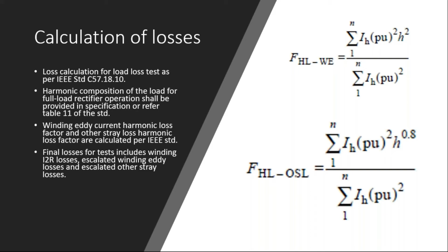And when it comes to testing, Parminder can talk about this, the additional losses we need to feed during the heat run test. Yeah, so based on the K-factor, harmonic losses are determined by engineering. For the temperature rise test, those are actually fed in addition to the load and no-load losses. The total losses which are fed during the temperature rise test are more than the total losses of the transformer which we generally calculate. So it is a combination of no-load losses plus the harmonics. That's how the temperature is simulated in the transformer.